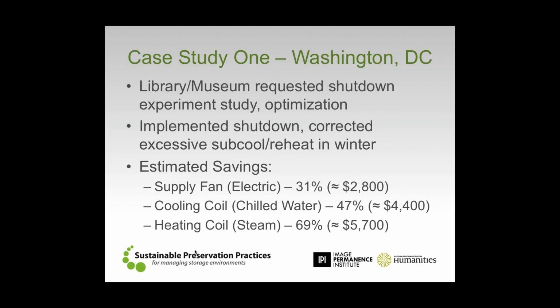Now, the other thing that we found when we started to go in and pull the data from the mechanical systems and the loggers that we had deployed is that they were trying to dehumidify throughout the entire winter. And even though Washington, D.C. doesn't feel like Rochester in January, there's still no need for dehumidification in D.C. in the wintertime. So by correcting that particular behavior and looking at the shutdown, just those 2 strategies right there, just finding those 2 opportunities, came up with estimated savings for, and this is for one particular unit, and this is where the numbers get a little bit interesting.